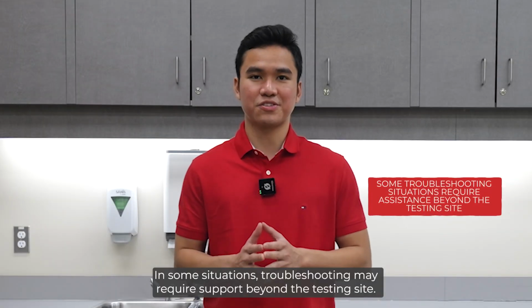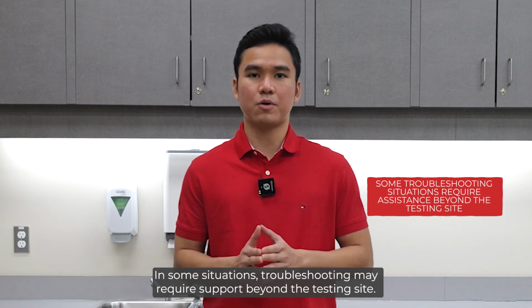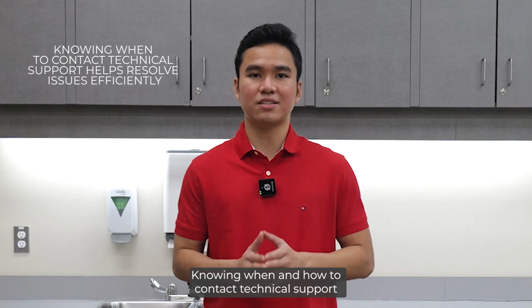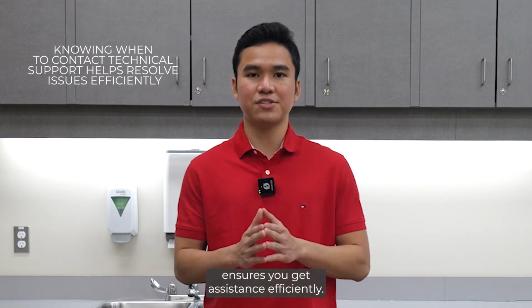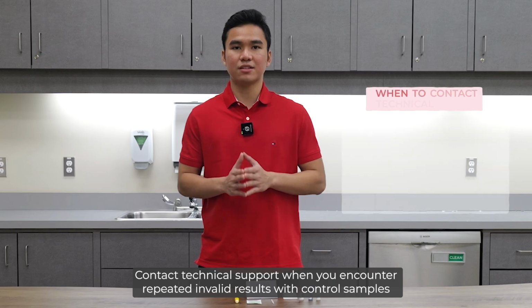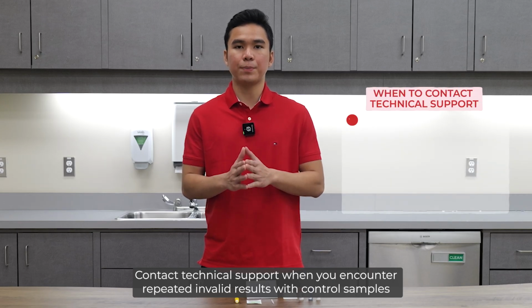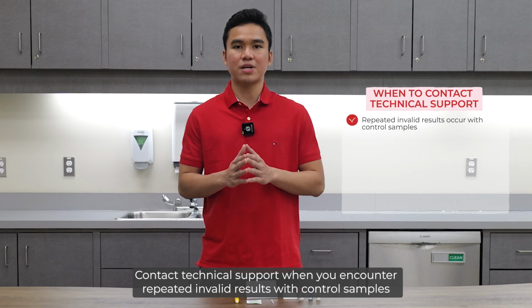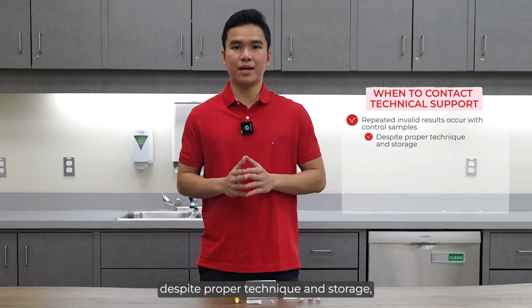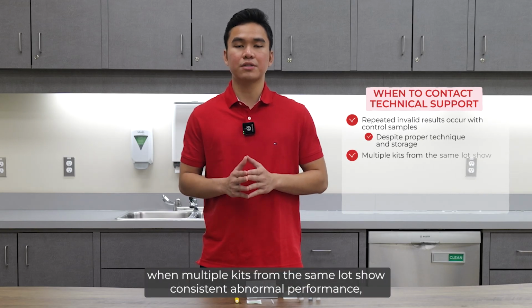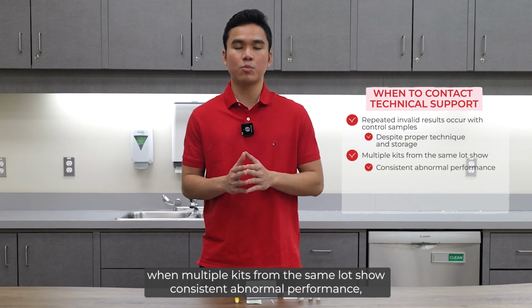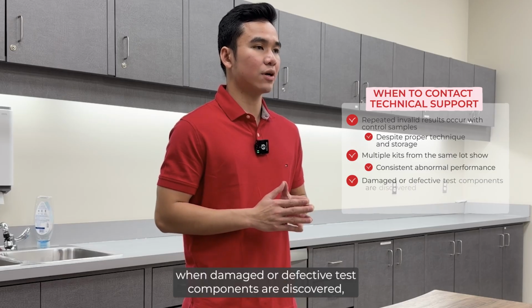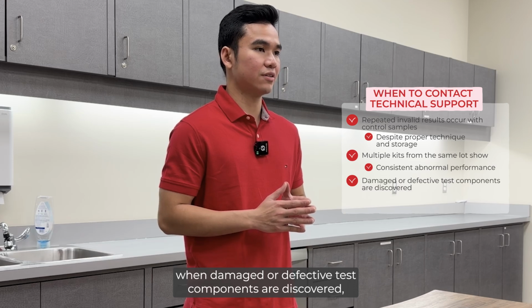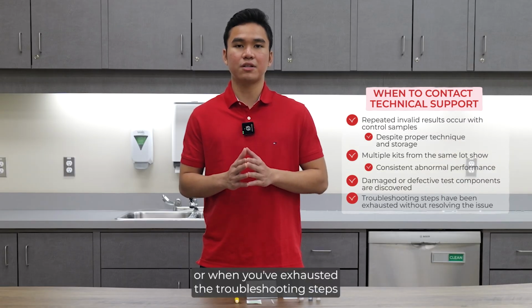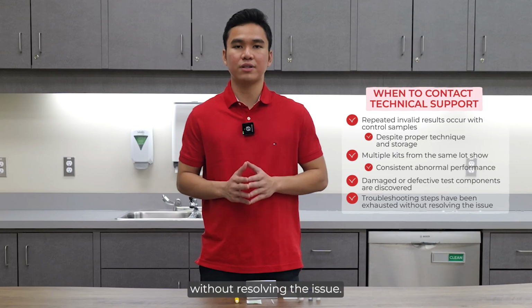In some situations, troubleshooting may require support beyond the testing site. Knowing when and how to contact technical support ensures you get assistance efficiently. Contact technical support when you encounter repeated invalid results with control samples despite proper technique and storage, when multiple kits from the same lot show consistent abnormal performance, when damaged or defective test components are discovered, or when you've exhausted the troubleshooting steps without resolving the issue.